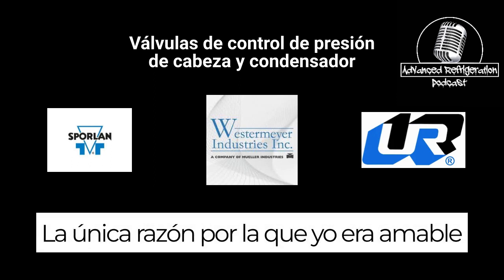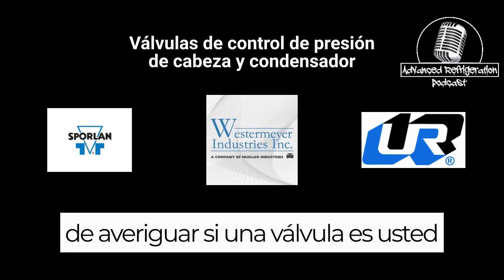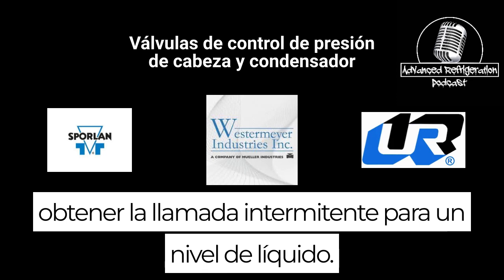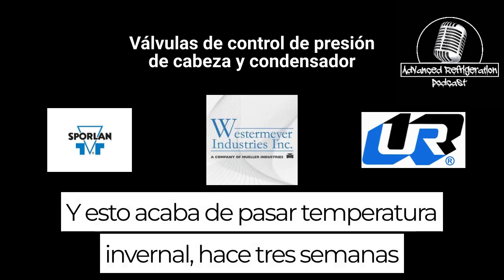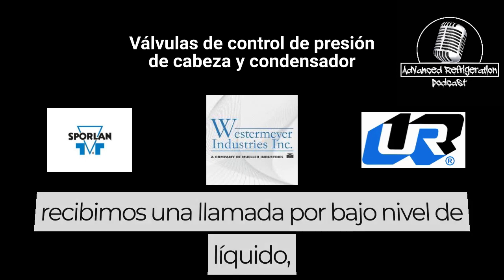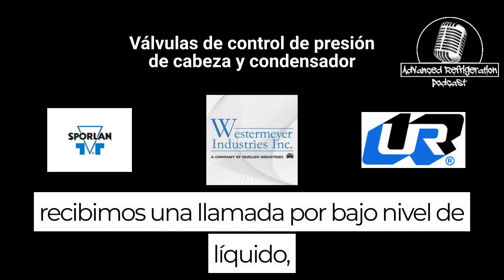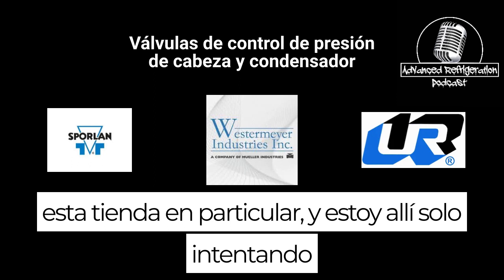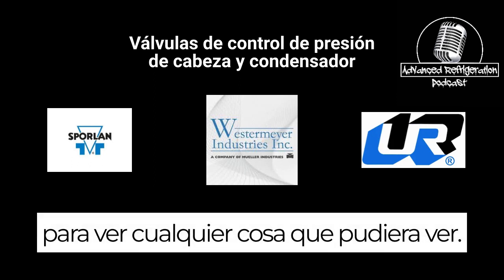The only reason I'm asking is that sometimes it's hard to figure out if a valve is the problem when you're getting an intermittent call for a liquid level. This just happened, it's wintertime, so it's the season. Like 3 weeks ago, we were getting a call for a low liquid level at this one particular store, and I was there just trying to see anything I could see.